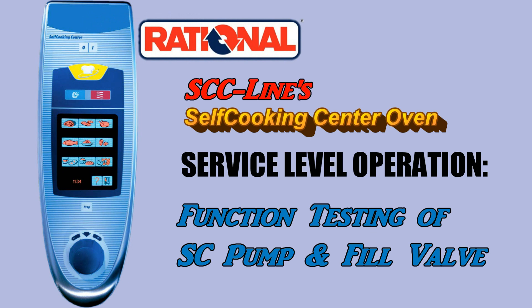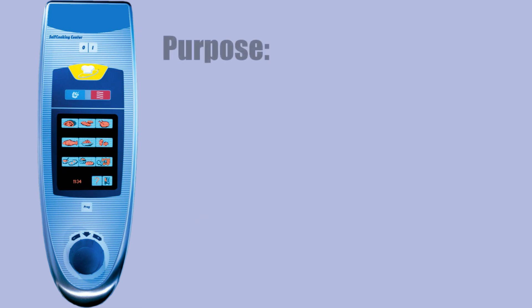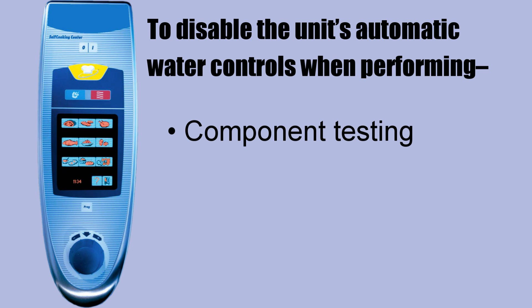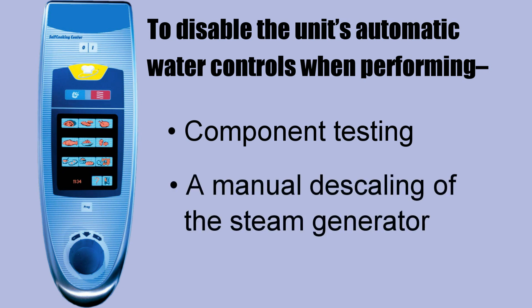The SCC self-cooking center oven service level operation for function testing covers the self-cleaning pump and the fill valve. The purpose of this procedure is to disable the unit's automatic water controls when performing component testing and to have complete control over the oven's functions during a manual descaling of the steam generator.